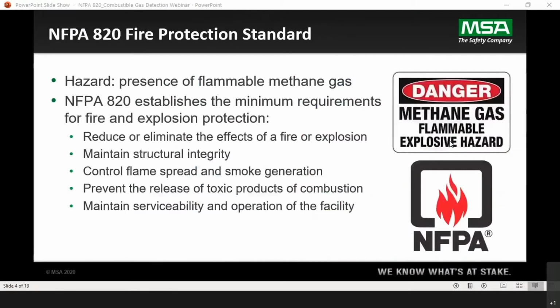So what is the NFPA 820 fire protection standard? The main hazard is the presence of flammable gas, methane. NFPA 820 establishes minimum requirements for fire and explosion protection. Some of the main points of the standard are to reduce or eliminate the effects of fire or explosion, maintain the structural integrity of plant infrastructure, control flame spread and smoke generation upon a fire, prevent the release of toxic products of combustion, which can also be very hazardous as these products are formed when fire exists, and maintain the serviceability and operation of the facility itself. Those are the basic requirements of 820.